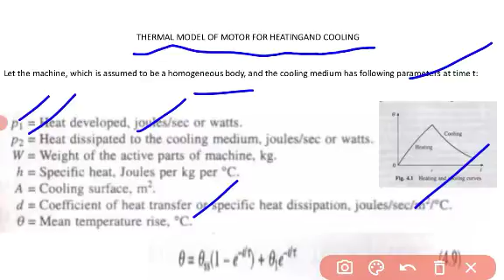Let P1 be the heat developed in joules per second or watts. P2 is the heat dissipated to the cooling medium in joules per second. W is the weight of the active part of the machine in kg. H is the specific heat in joules per kg per degree centigrade. A is the cooling surface area in meter square. D is the coefficient of heat transfer or specific heat dissipation, in joules per second per meter square per degree centigrade. Theta is the mean temperature rise in degree centigrade. With this, we can write this equation. I will show you in the next slide.